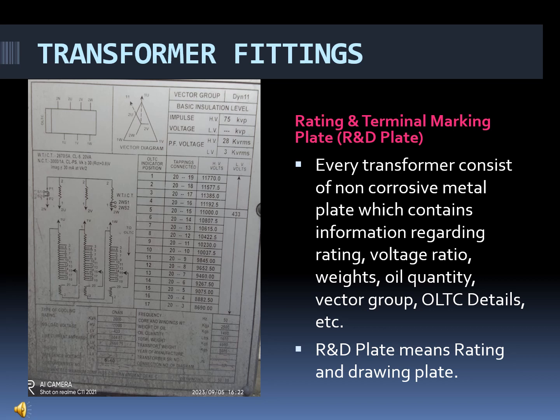On this metal plate, we will have information regarding the rating, voltage, weight, oil quantity, vector group, OLTC details, and basic insulation levels. Apart from this information, some other information is contained in the transformer nameplate. Please go through this transformer nameplate. As per the transformer nameplate, the rating and terminal marking plate will be mentioned in almost all transformers.